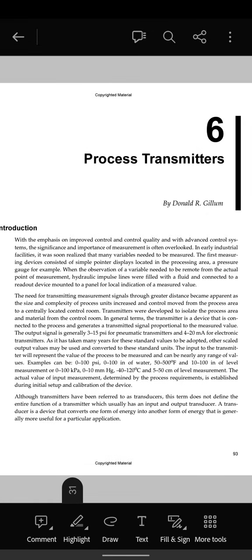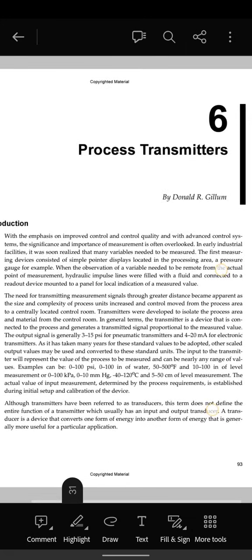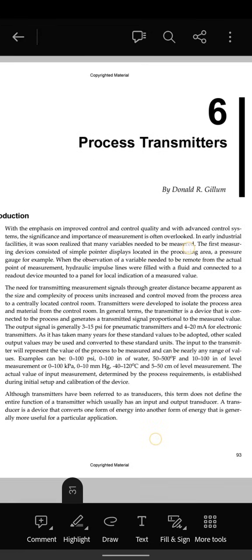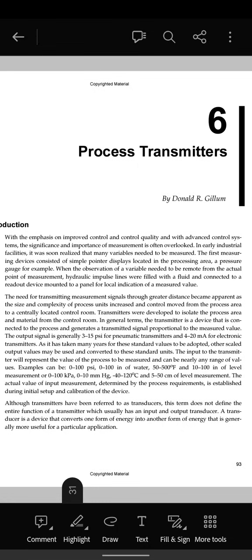The need of transmitting measurement signals through greater distances became apparent as the size and complexity of process units increased, and control moved from the process area to a centrally located control room. Transmitters were developed to isolate the process area and material from the control room. In general terms, the transmitter is a device that is connected to the process and generates a transmitted signal proportional to the measured value. The output signal is generally 3 to 15 psi for pneumatic transmitters, and 4 to 20 mA for electronic transmitters. It has taken many years for these standard values to be adopted. Other scaled output values may be used and converted to these standard units.